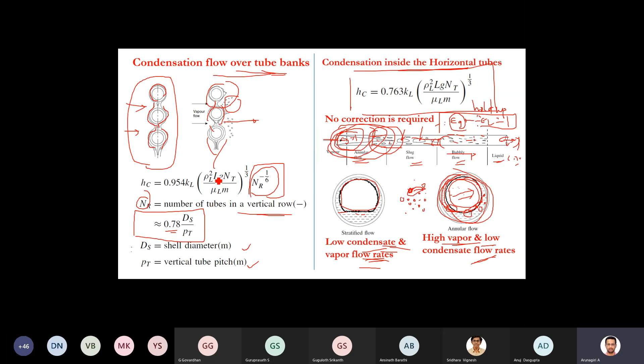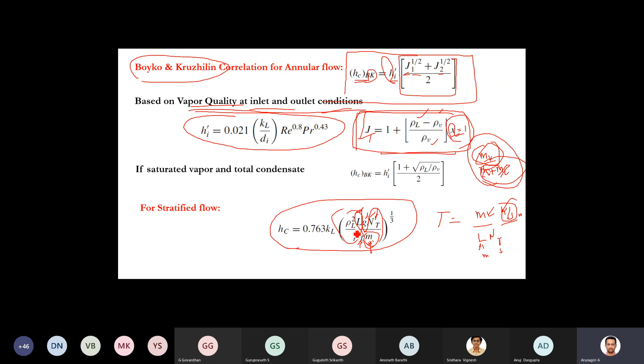So for inside and outside vertical tubes, the condensate loading is different. In the previous case it's L, because it is a horizontal one, so we talk about the length it is passing through. But in this vertical case, we have to talk about inside and outside. So the condensate loading is different for horizontal tubes and vertical tubes. For vertical tubes, it is WC by NT π d_o when condensation takes place outside the tube, and WC by NT π d_i when condensation takes place inside. So these are all design equations that can be used.